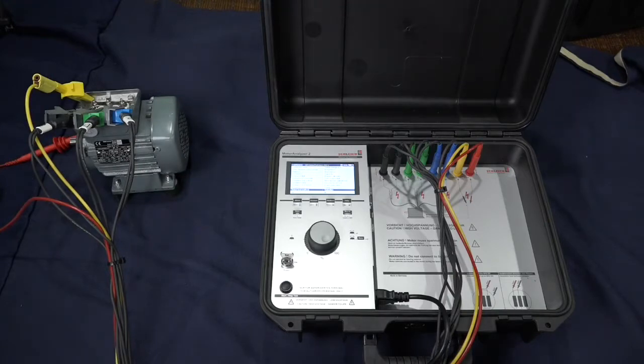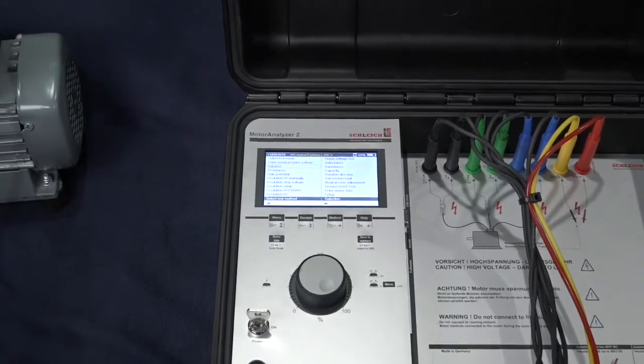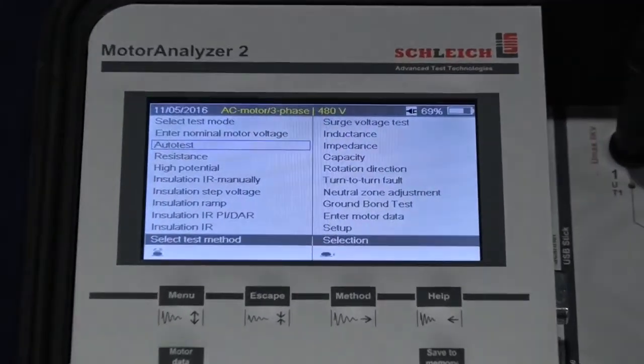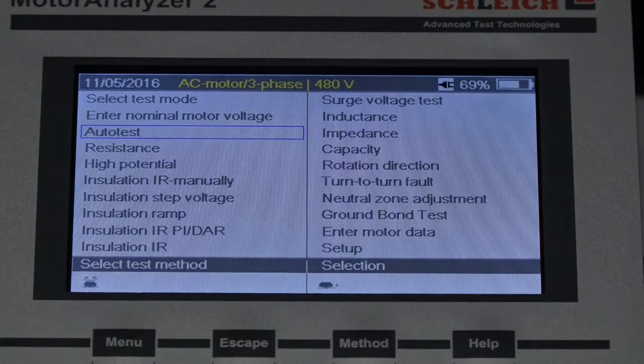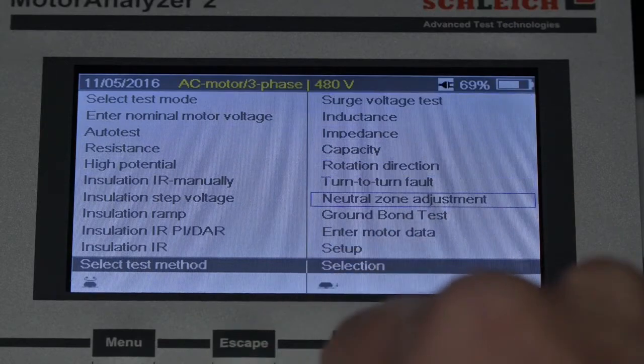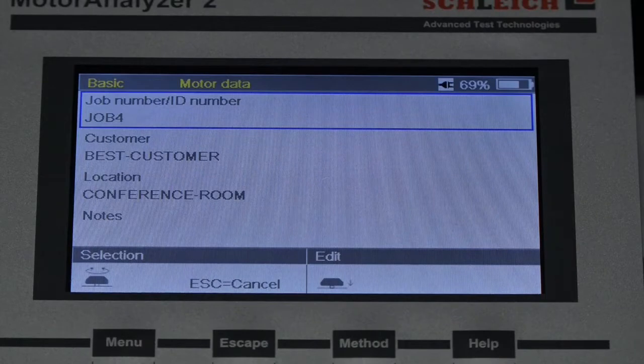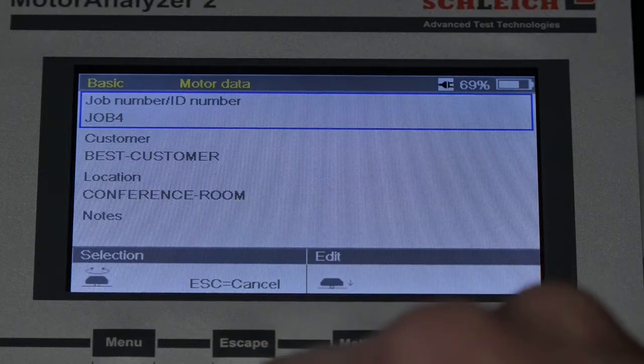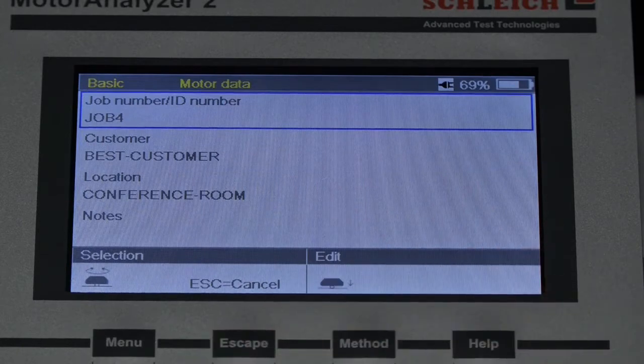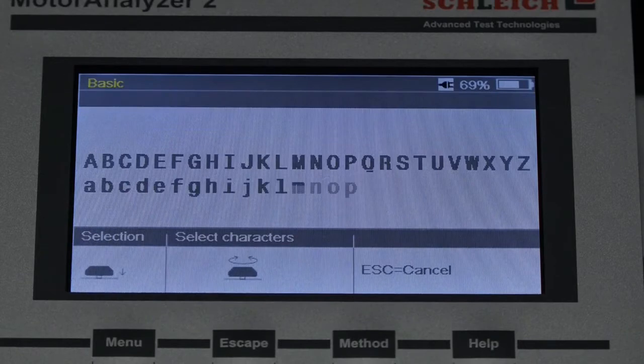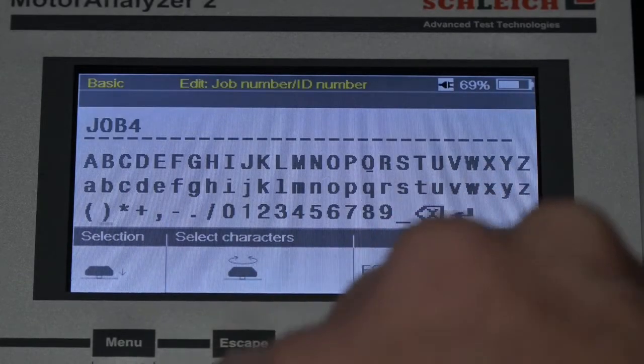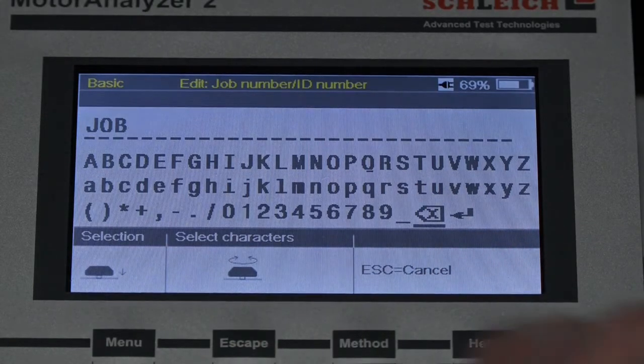Next, let's enter some information about this stator, and we'll tell the instrument how we want it to test. So let me zoom in on the screen here so you can see what I'm doing. Using the whiz wheel, I will move down over here to the option that says Enter Motor Data. Here we have 4 fields: a job number, a customer, a location, and a note field. So let's use the whiz wheel to edit these things. I'm going to change my job number from job 4 to job 5. So I'll use the whiz wheel, select the center, and use the delete key, and add a 5. There we go.